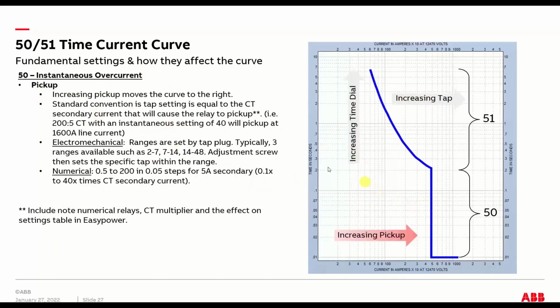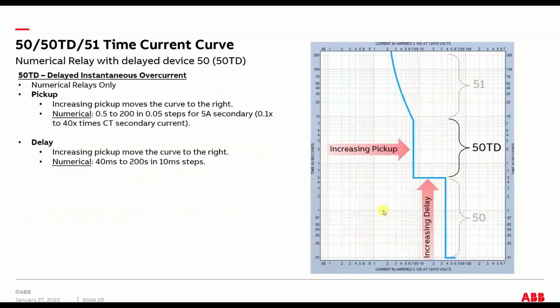Your 51, or your 50, is then this part of the curve down here, and that typically only has a pickup value. It may have a range that's set plus the pickup value, but as you have increasing pickup, that moves this part of the curve to the left or the right in terms of amps. And all this stuff carries forward into the numerical relay, with all the same terminology.